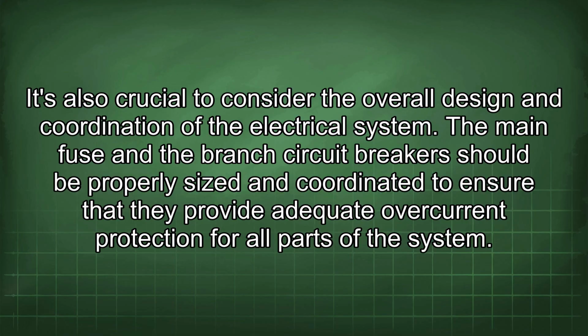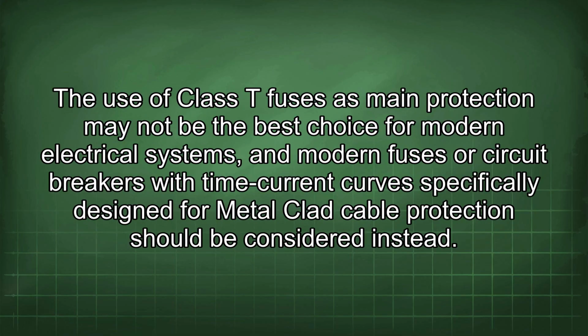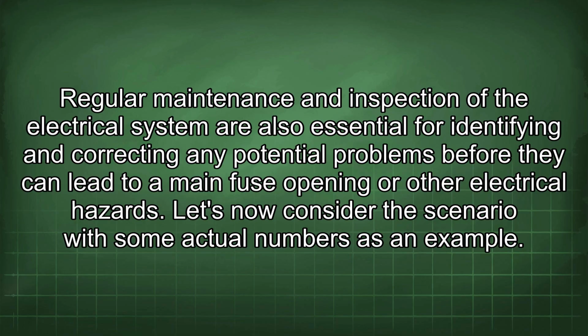The main fuse and the branch circuit breakers should be properly sized and coordinated to ensure that they provide adequate overcurrent protection for all parts of the system. The use of Class T fuses as main protection may not be the best choice for modern electrical systems, and modern fuses or circuit breakers with time current curves specifically designed for metal-clad cable protection should be considered instead. Regular maintenance and inspection of the electrical system are also essential for identifying and correcting any potential problems before they can lead to a main fuse opening or other electrical hazards.